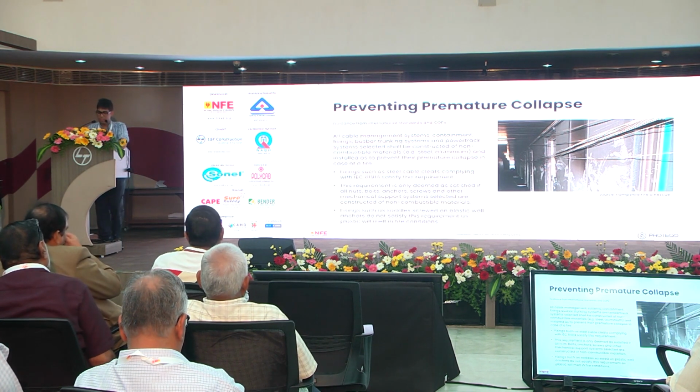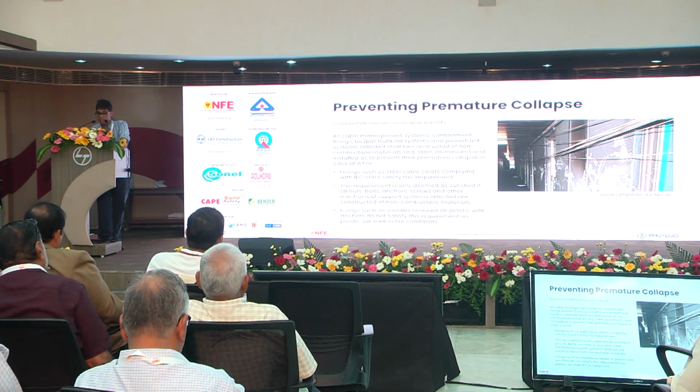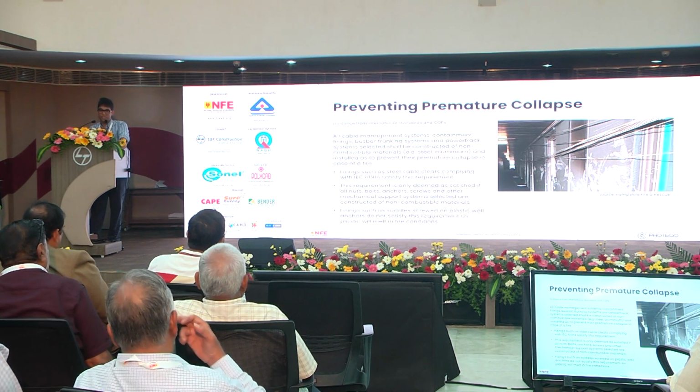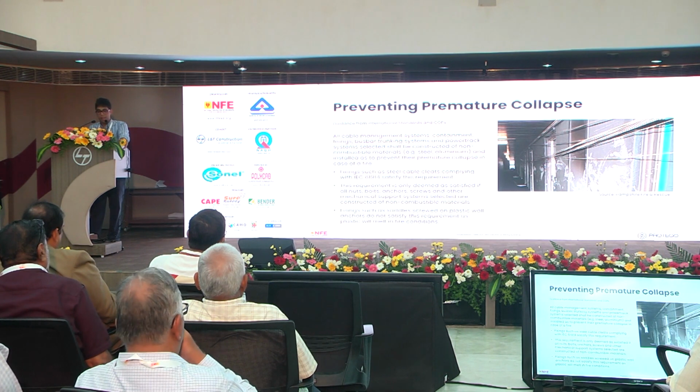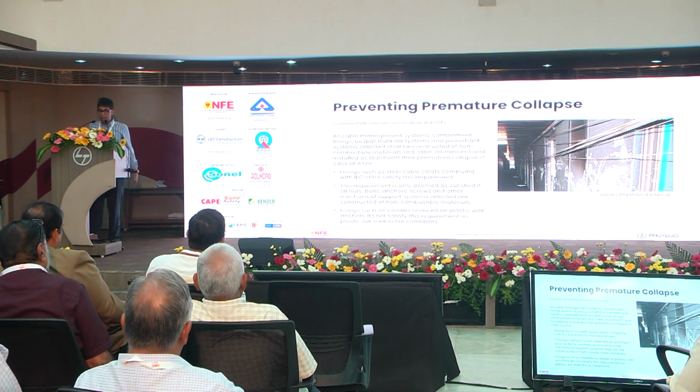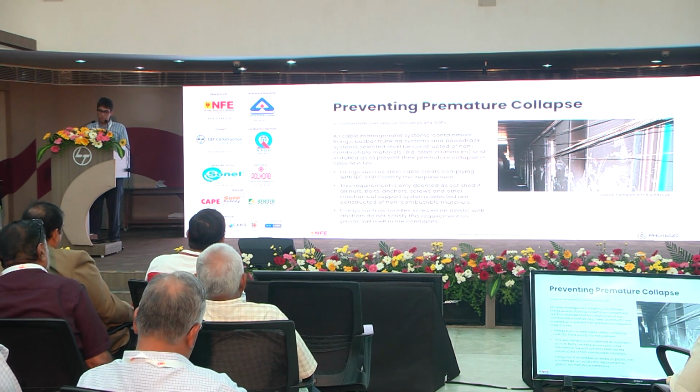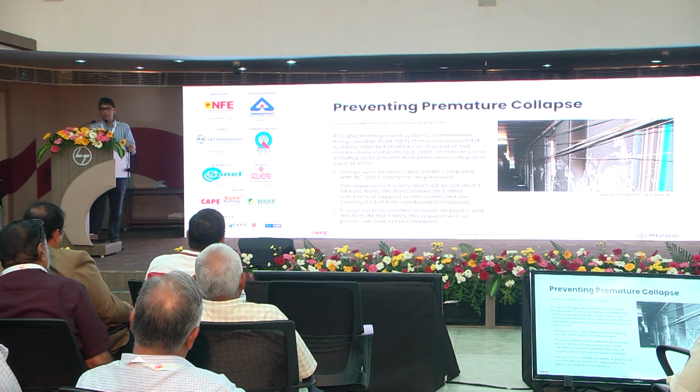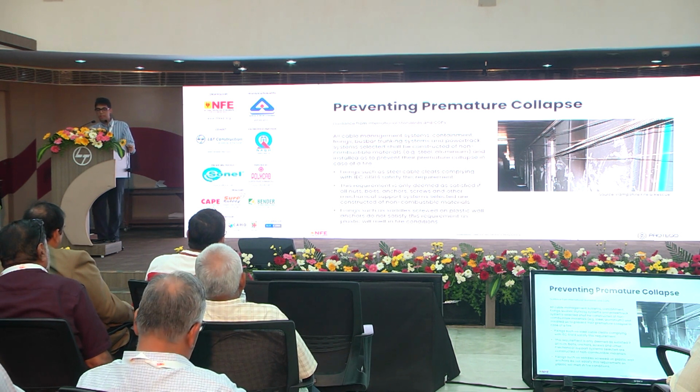There was a very famous incident in the UK called the Shirley Towers incident. You can see in front of the doorways what has happened. They used plastic fixings and all the cables came down. Now in a smoke-filled environment, you will not see this. This thing is piping hot, you will get burnt. So what should you do? Use a cable cleat that complies with 61914, a steel cable cleat.